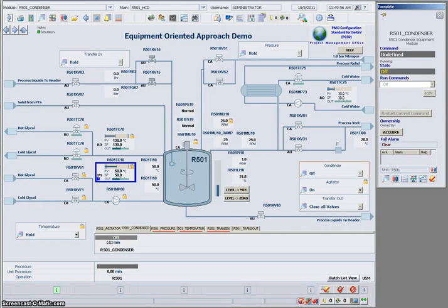What the studies have found is that there is an abundant use of color throughout the graphics. Many facilities use different colors such as red and green to indicate the status of motors, pumps, and valves. They use bright colors for bar graphs and measurements. They also change the lines to reflect the contents, and oftentimes the choice of colors, again, is bright. The overall result is that the operator has a lot of visual information but cannot necessarily discern what is important due to an abnormal situation versus what is everyday.